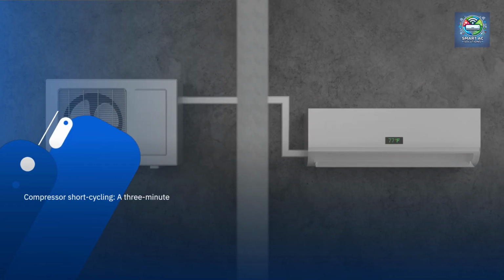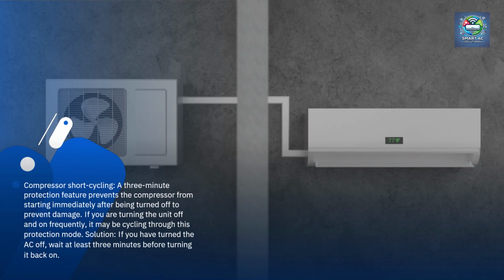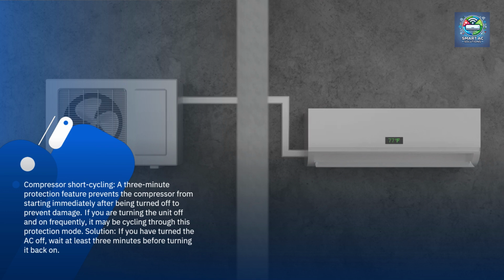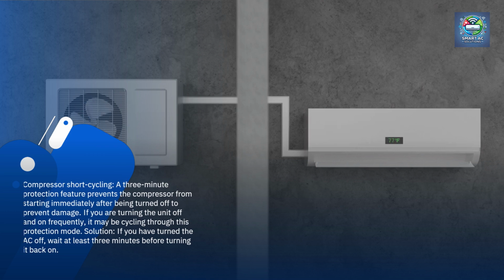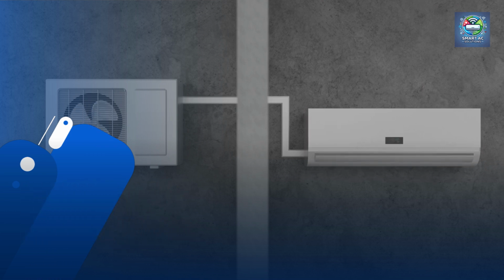Compressor short cycling. A 3-minute protection feature prevents the compressor from starting immediately after being turned off to prevent damage. If you are turning the unit off and on frequently, it may be cycling through this protection mode. Solution: if you have turned the AC off, wait at least 3 minutes before turning it back on.